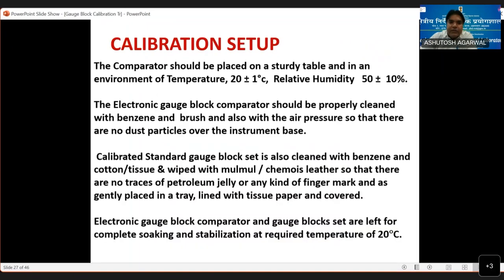So calibration setup, what we need to calibrate: the calibrator should be placed on a steady table. That table should not move, should not have some vibration or some kind of movement like this. Environment and temperature should be 20 degrees, plus or minus 1 is allowed. Humidity 50 RH, plus or minus 10 is allowed. So the electronic gauge comparator should be properly cleaned with benzene. Okay, so people put grease or WD-40 or something like this to prevent it from rust.